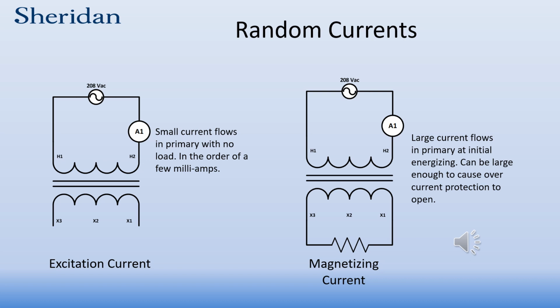Keep in mind too that if it's greater than 3%, you probably have a turn-to-turn short in the transformer. These large inrush magnetizing currents, large current that flows into the primary at the initial energizing of the transformer, could actually cause the overcurrent protection to open. Keep in mind though that this can be intermittent. It all depends on when you energize the transformer.